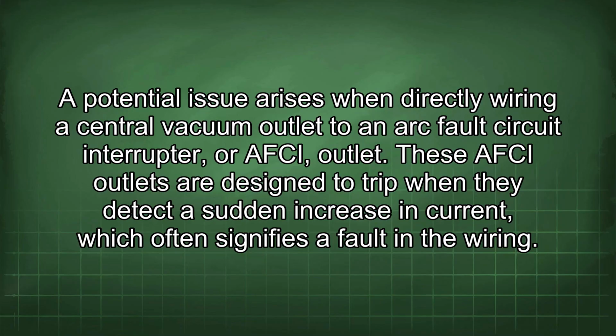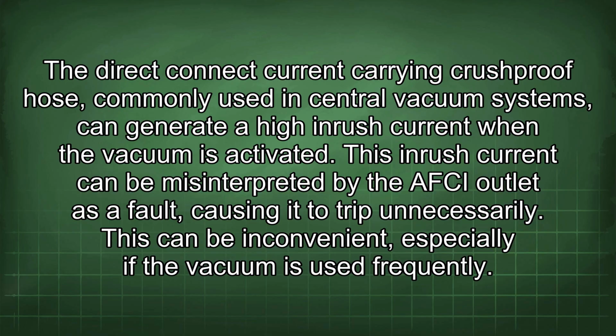A potential issue arises when directly wiring a central vacuum outlet to an arc fault circuit interrupter, or AFCI outlet. These AFCI outlets are designed to trip when they detect a sudden increase in current, which often signifies a fault in the wiring. The direct connect current carrying crush-proof hose, commonly used in central vacuum systems, can generate a high inrush current when the vacuum is activated. This inrush current can be misinterpreted by the AFCI outlet as a fault, causing it to trip unnecessarily. This can be inconvenient, especially if the vacuum is used frequently.